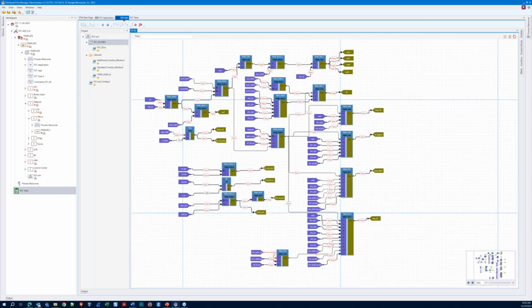Taking a peek inside of that 61131 file, here's that function block diagram that I described before. This is something that describes really the exact behavior for a specific distance protection algorithm. As I said before, it's made up of inputs, outputs, and what I call elementary operators - ands, ors, timer on delays. If you're familiar with PLC logic or controls and automation programming, hopefully it should look pretty familiar.